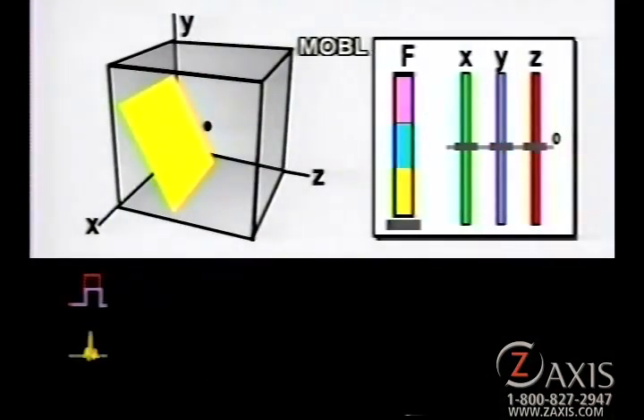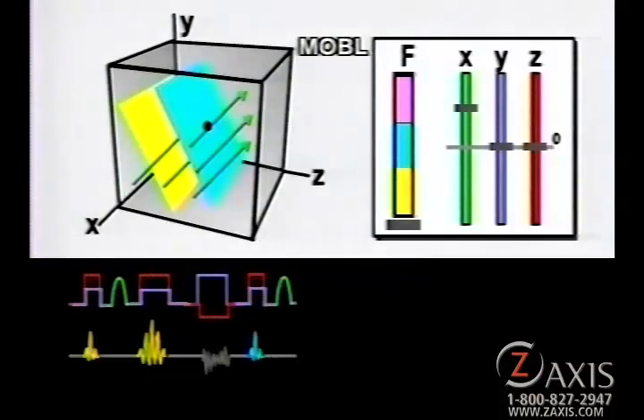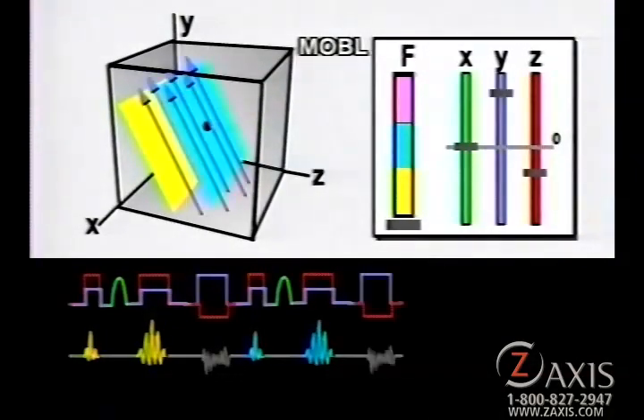In the multiple image oblique mode, the gradient coils are fired in pairs to rotate the gradient fields. As different frequencies of RF are applied, the image plane moves at an angle through the scanning volume.